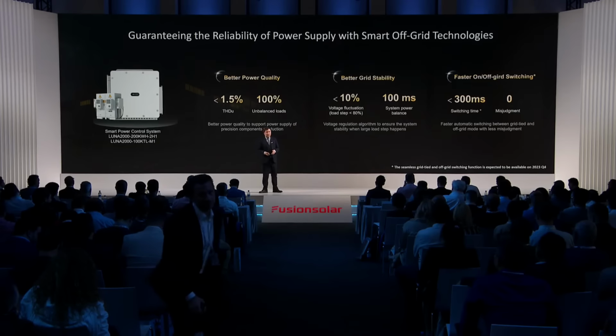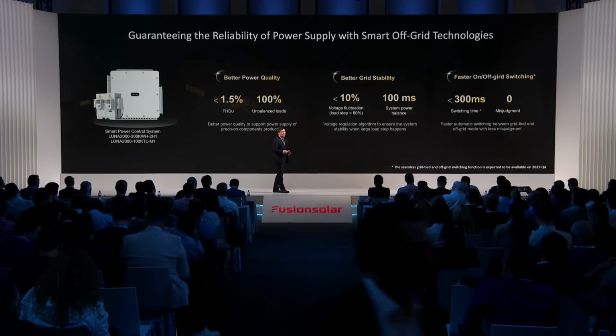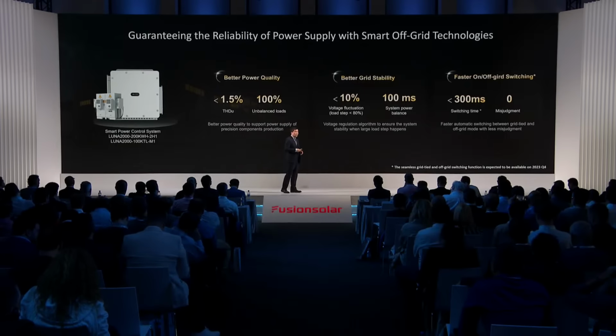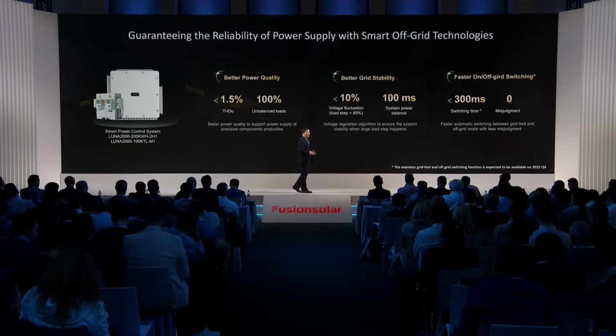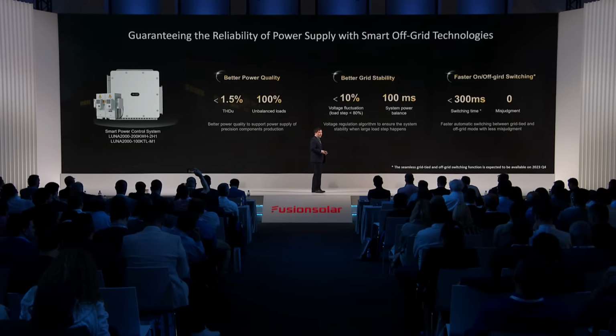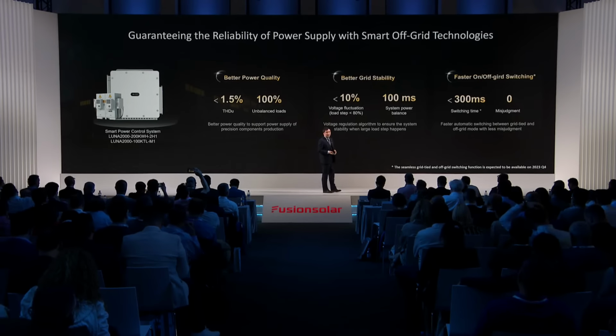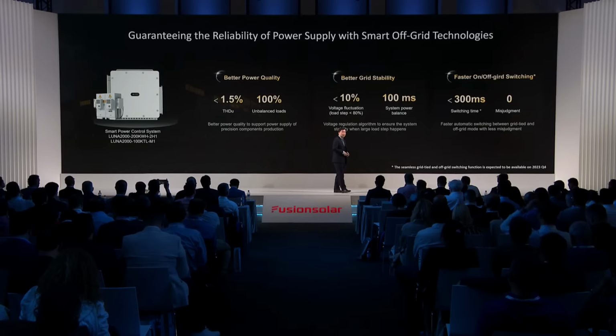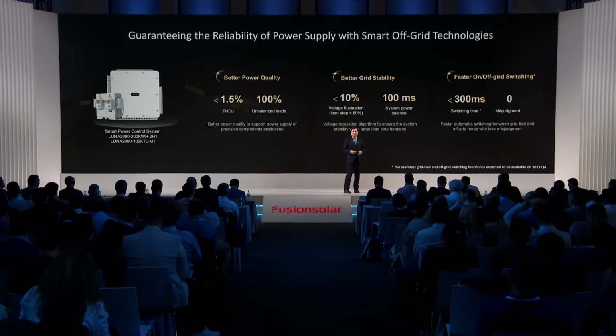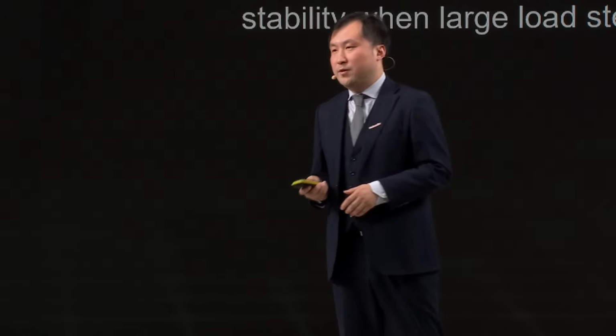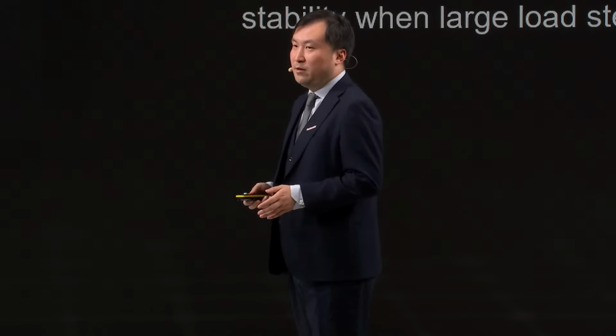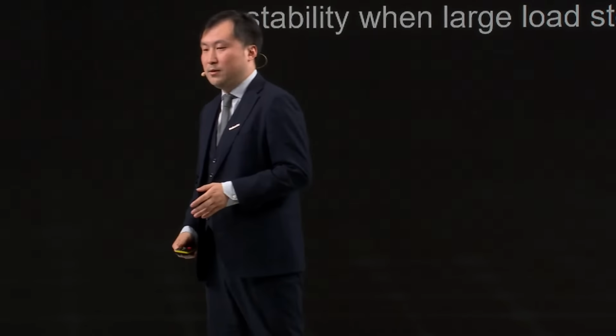During steady operation, with our unique smart harmonic control algorithm and grid forming capability, Huawei can support up to 100% of three-phase unbalanced resistive load. We can also ensure the THDU is within 1.5%, sometimes even better than the grid regulation requires.